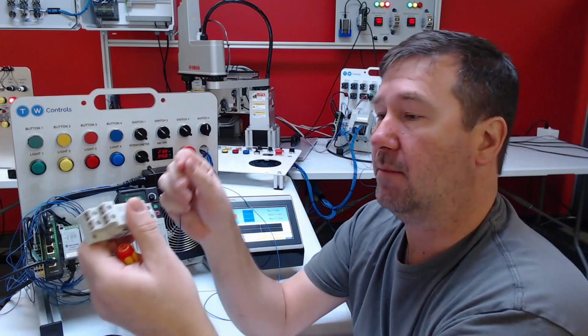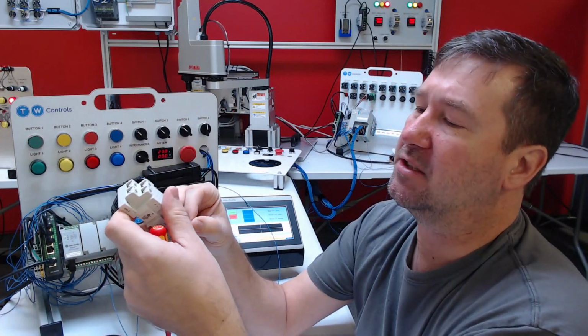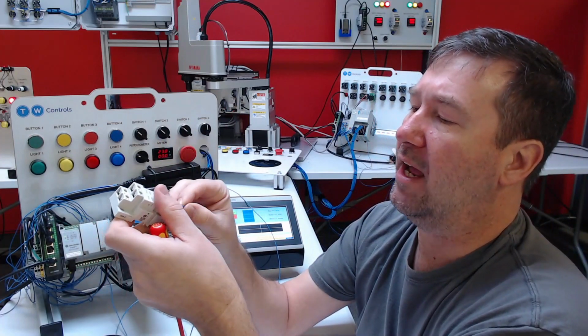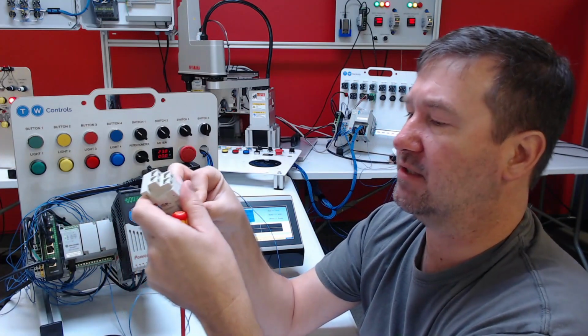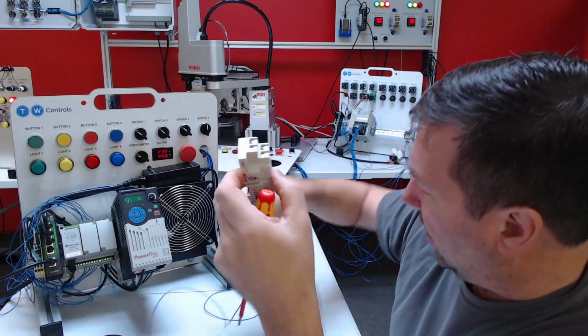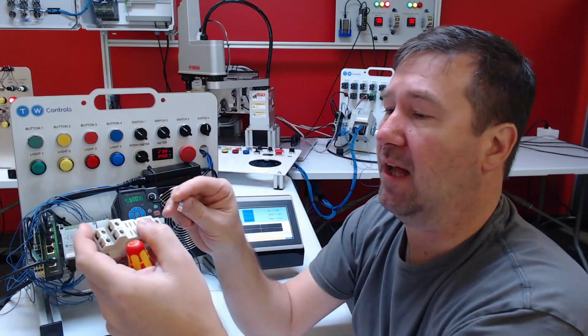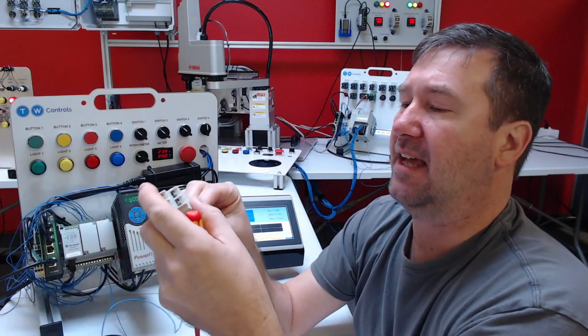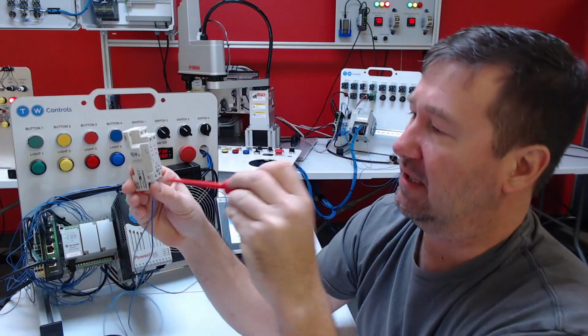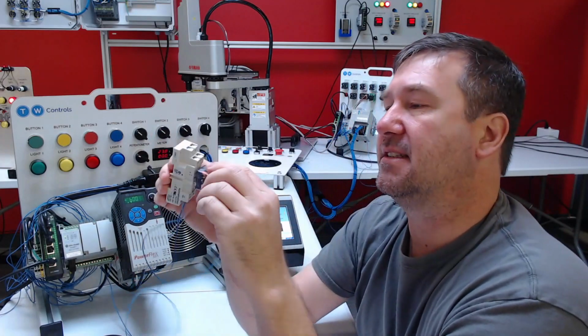I have a wire to output number 4 on the Micro820, and I'm going to connect it to terminal number 13, or A1, which is that right terminal. And then I have a wire from our minus DC power supply, and I'm going to connect it to A2, or terminal number 14. And now I'm going to plug my relay into the socket.